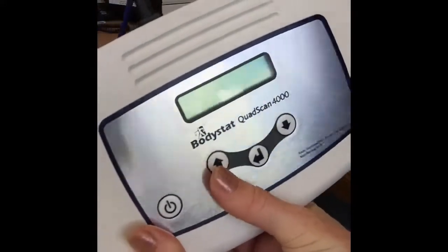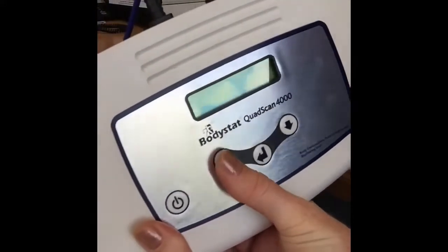In this video, I'm going to show you the installation mode within the Bodystat Quadscan 4000 unit. Within this installation mode, you have the option of changing the display on the LCD screen.